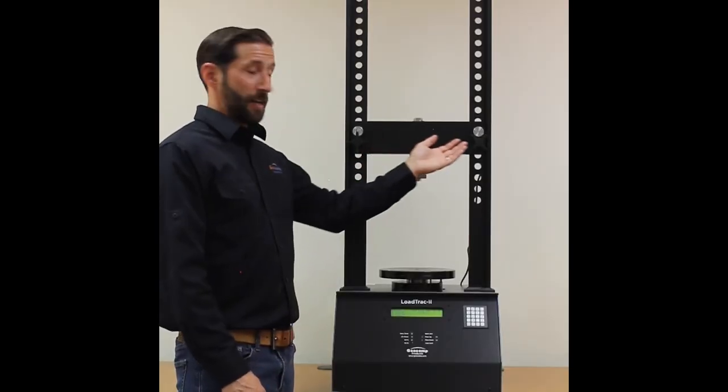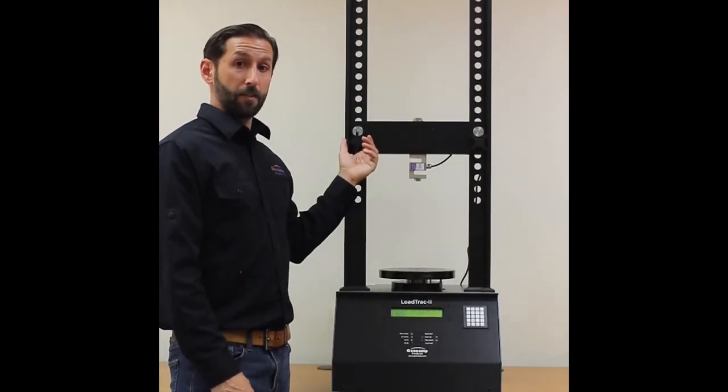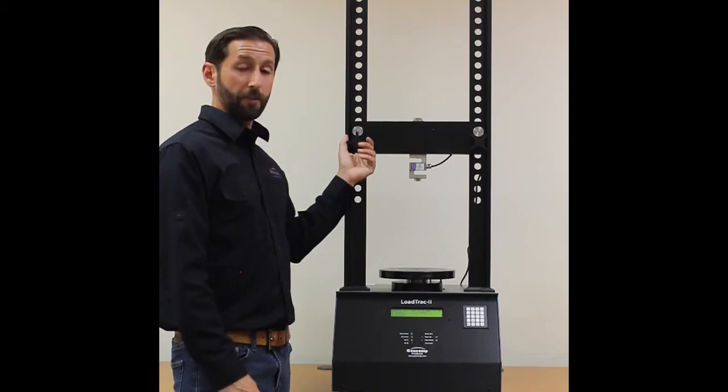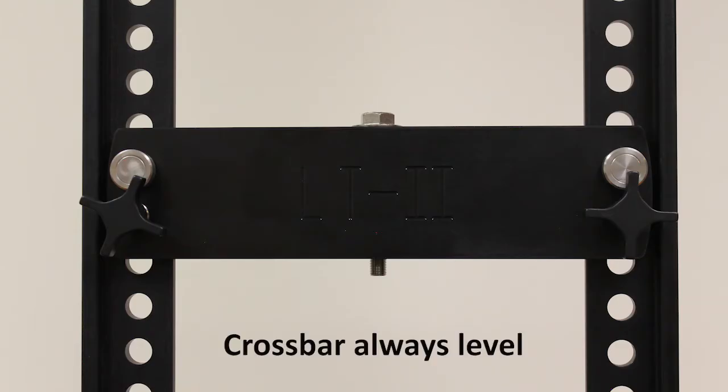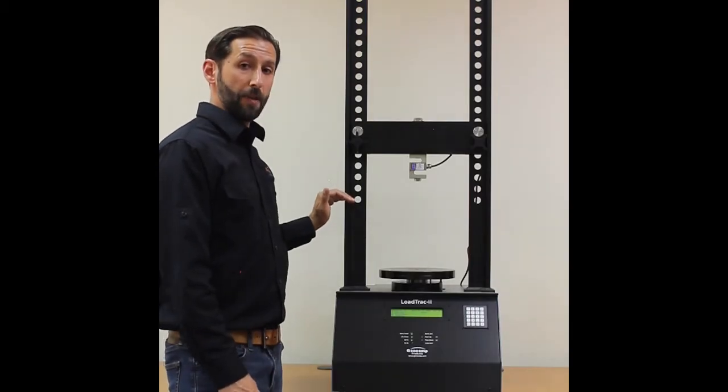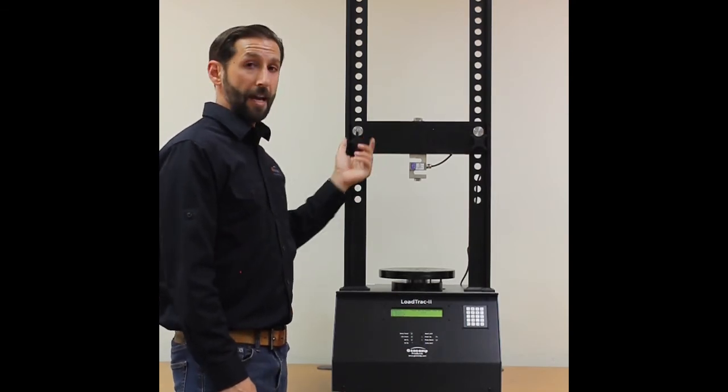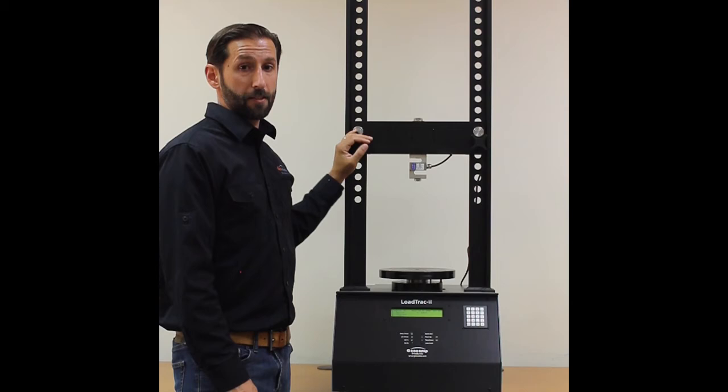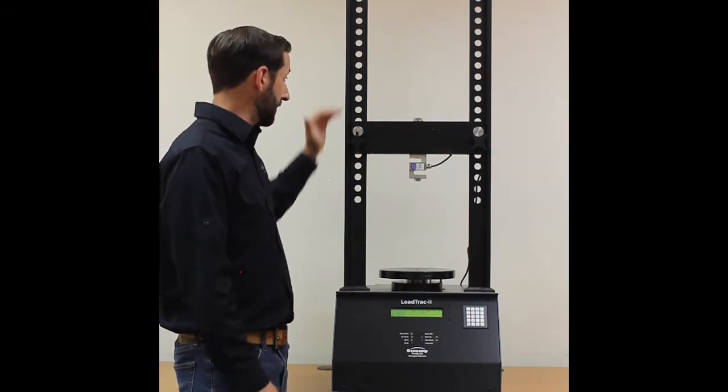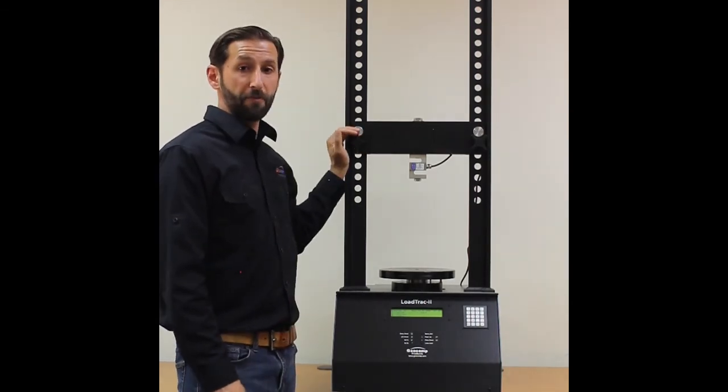We have our crosshead, which is very easy to move and incorporates a set of compression pins and secondary pins to stabilize the crossbar. Using these, you can quickly move it for any test type you may be operating on the machine. This is much better than having the threaded uprights that can take a considerable amount of time to position where you want to be for your test.